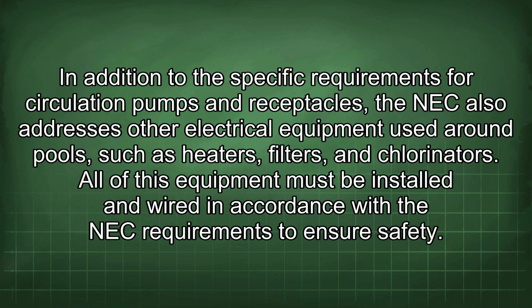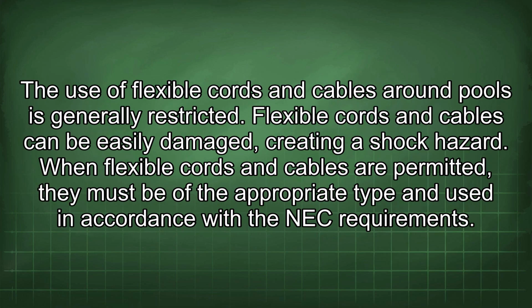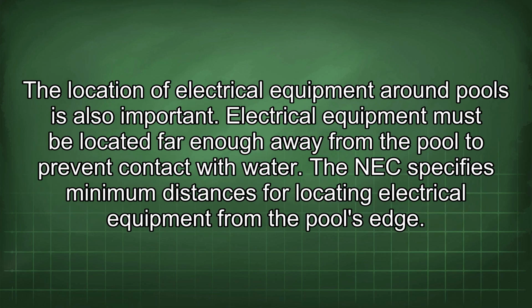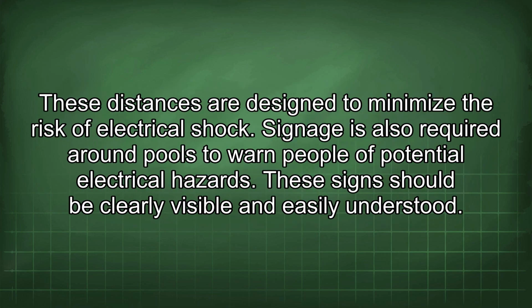All of this equipment must be installed and wired in accordance with the NEC requirements to ensure safety. The use of flexible cords and cables around pools is generally restricted. Flexible cords and cables can be easily damaged, creating a shock hazard. When flexible cords and cables are permitted, they must be of the appropriate type and used in accordance with the NEC requirements. The location of electrical equipment around pools is also important. Electrical equipment must be located far enough away from the pool to prevent contact with water. The NEC specifies minimum distances for locating electrical equipment from the pool's edge. These distances are designed to minimize the risk of electrical shock.